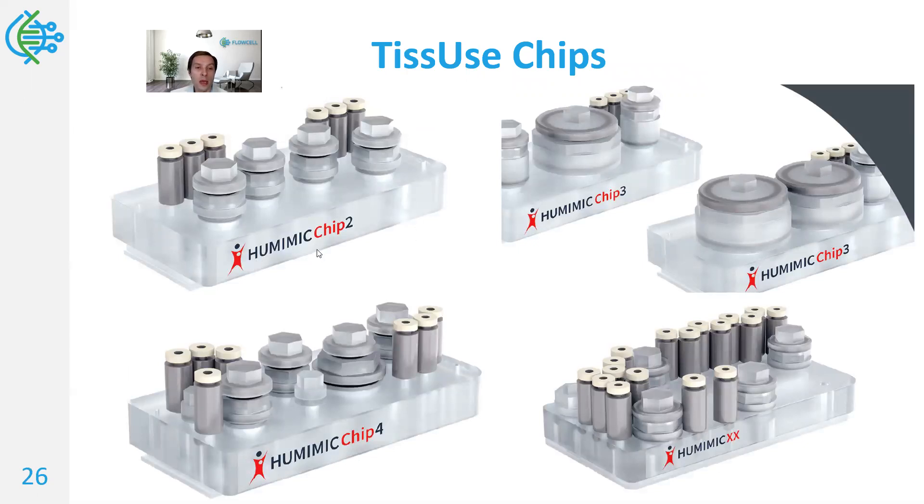There are HUMIMIC chips 2, 3, 3+, 4, and some others. These chips have multiple ports — as you saw from the schematic, they have two organ compartments each that can be connected. HUMIMIC chips 3 have a 3-port configuration for additional sequencing of different tissues — it could be liver, kidney, and then some other organ type. As you can see, the top access ports vary in design, giving the user more flexibility, and the company is also able to do rapid prototyping to customize chips if necessary.